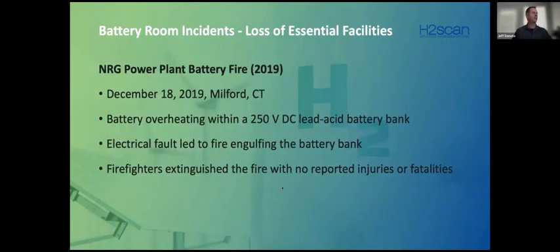Another loss of facilities was an NRG power plant in 2019. This was a lead acid battery bank. An electrical fault led to a fire, and they extinguished this with no injuries. But again, in this case, hydrogen may have been a contributing factor, which of course led to a fire within that facility.